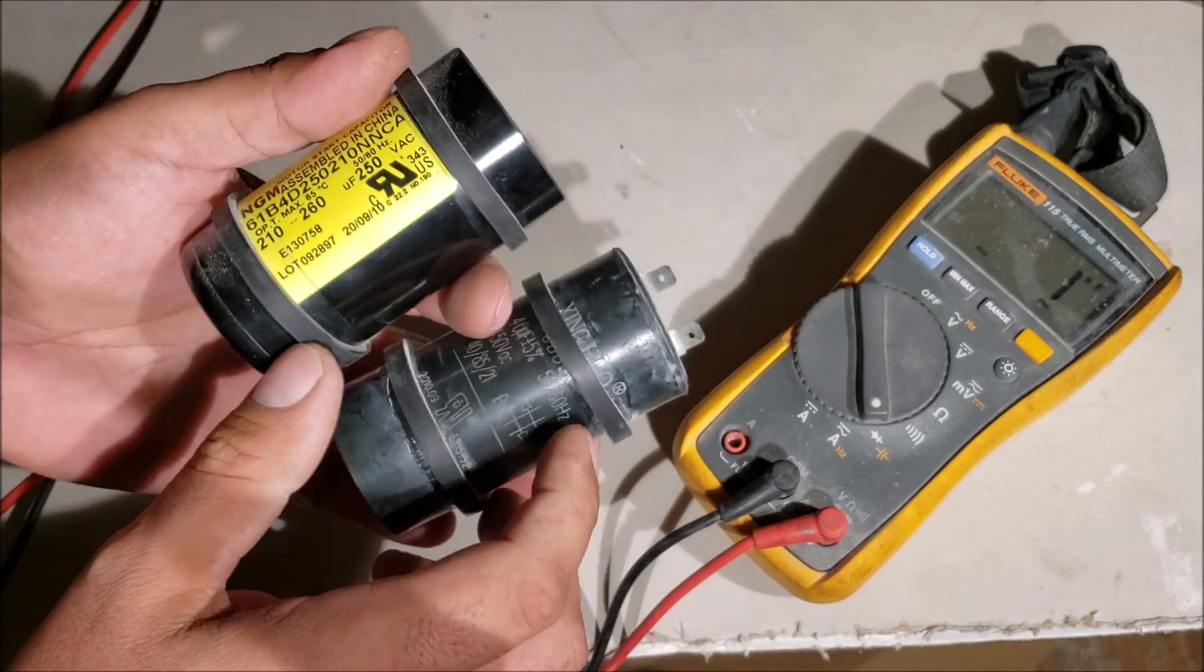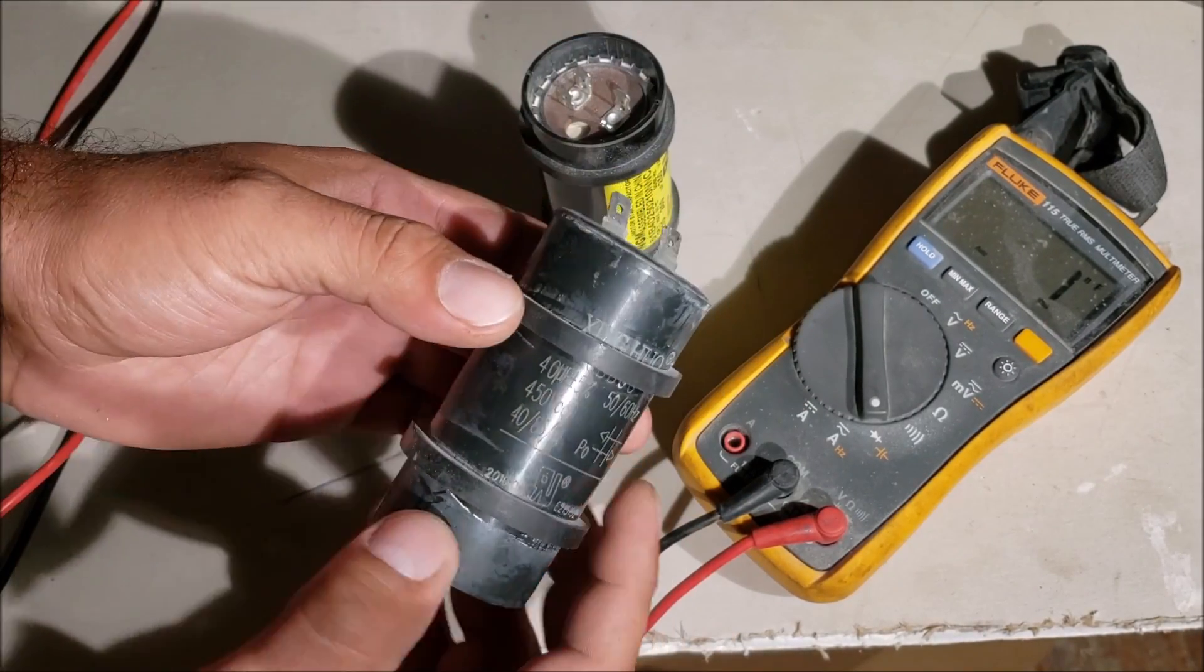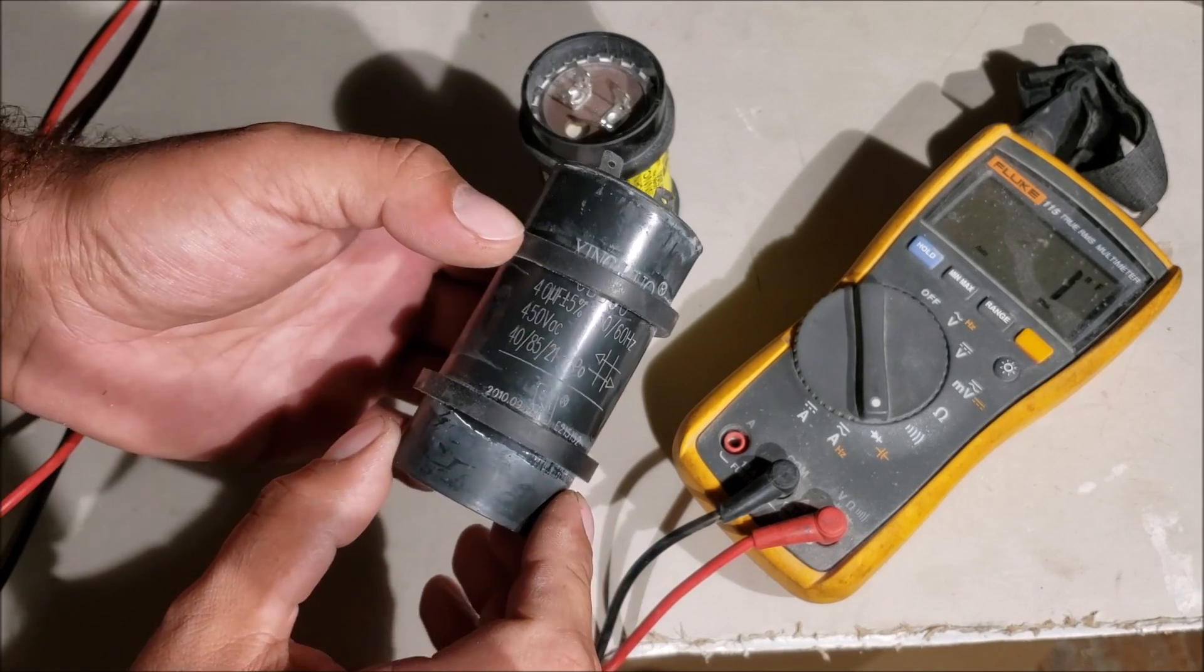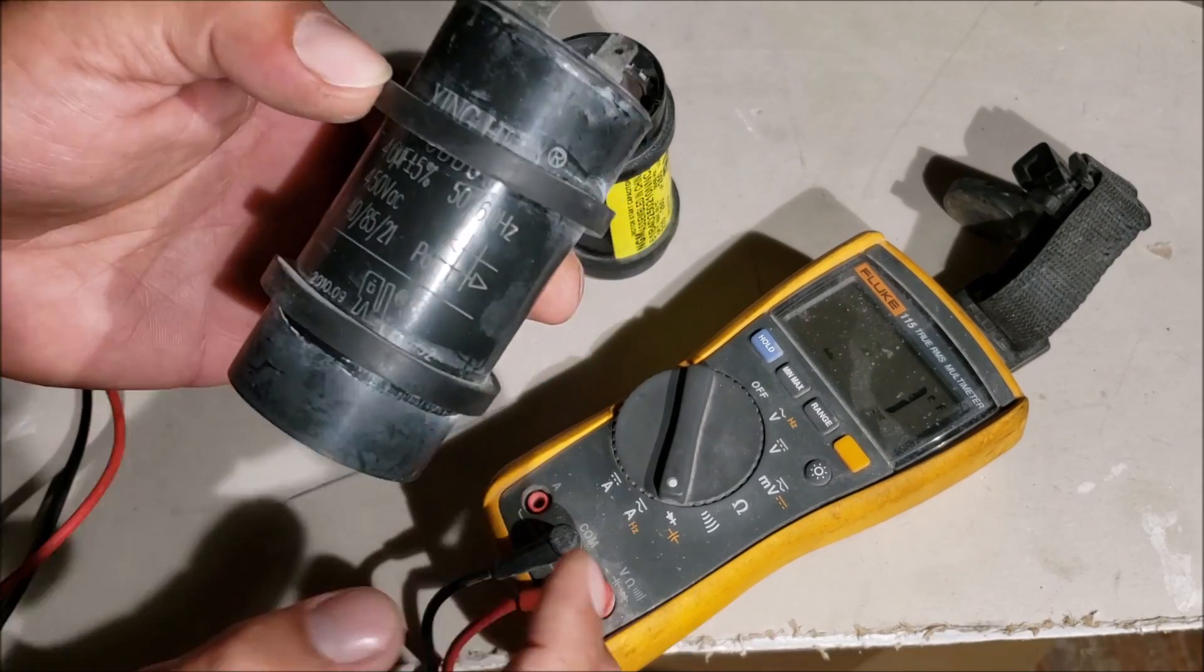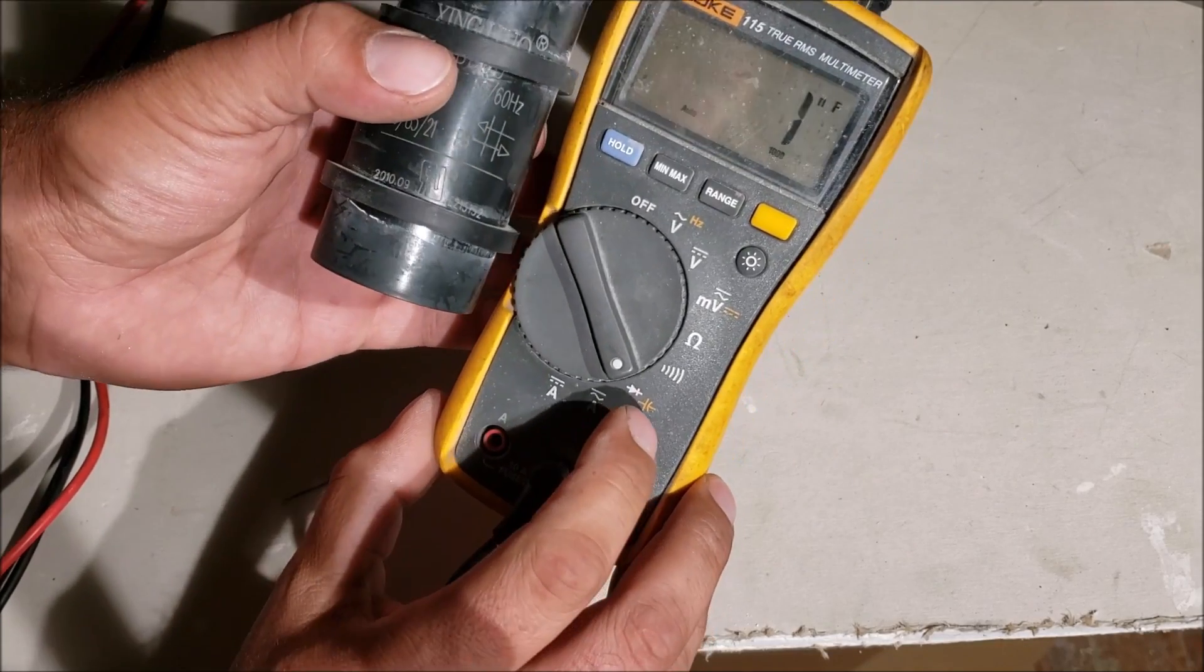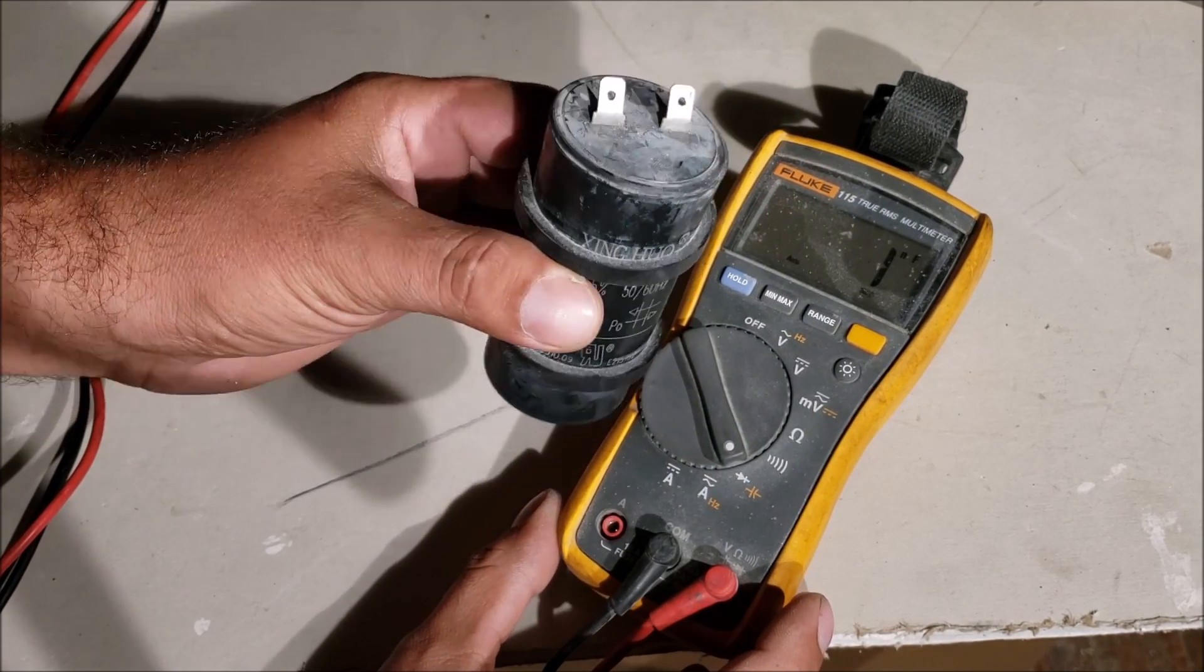We're looking for 38 to 42, we're getting 35.5 microfarads. So this run capacitor is actually bad. That's why it's very important to test the capacitance with the correct meter, because the other two tests we're not going to be able to check that like we did. We've got two good ones and one bad one.